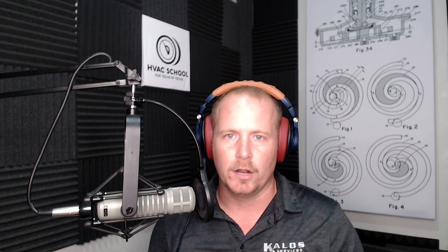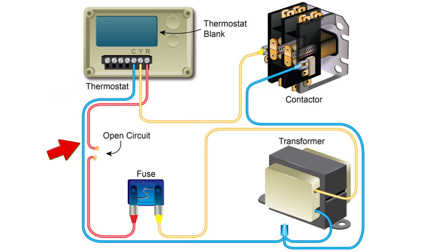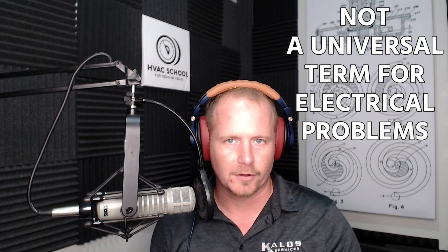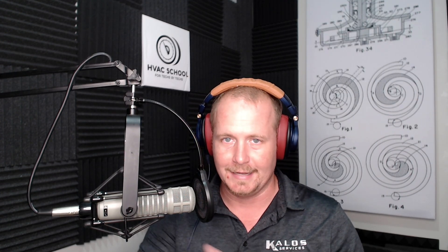So you walk up and the thermostat's calling for cooling, but the contactor is not pulling in — that's a case of an open circuit. Now, where it gets confusing is that a lot of people use the term 'short,' which is something totally different, as a universal term for electrical problems. It is not. A short is a specific problem.